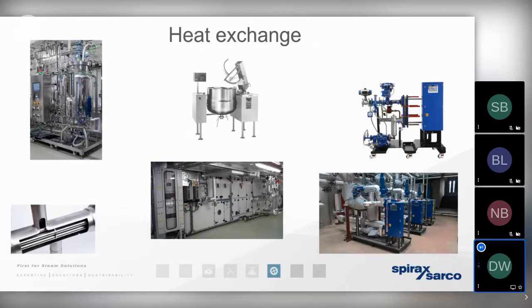So it bears mentioning that steam can be used in a number of direct injection processes, for example, humidification, or if it's being used for injection directly into a vat of water, for example. And in those cases, the steam and also the condensate becomes consumed in the process. So for direct injection processes, there simply isn't going to be any condensate to recover anyway.